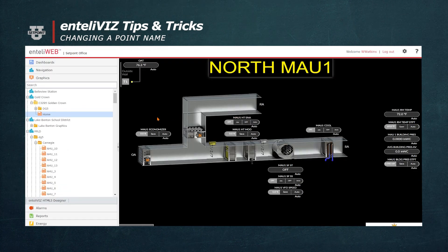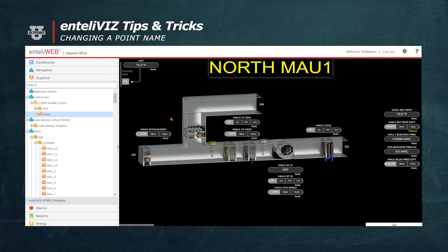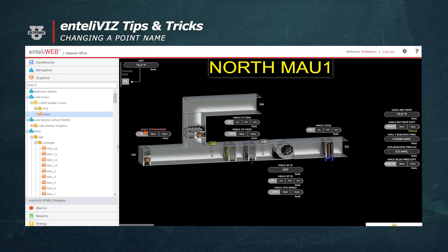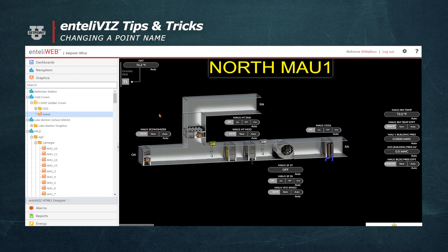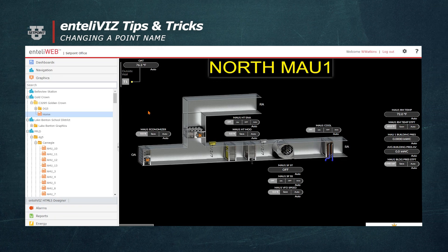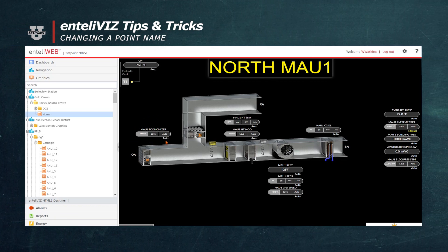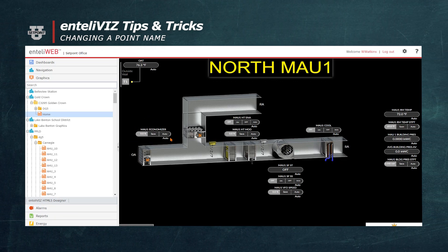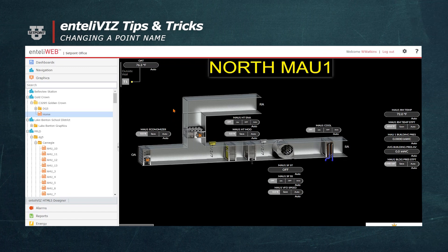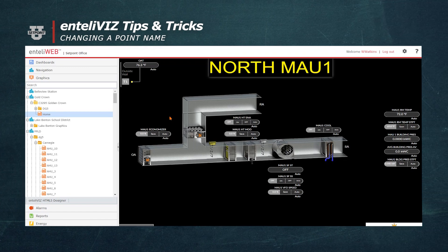This is because when these points are linked to the graphic, they assume the name of the object. It brings the name in at the same time, so in order to change it, you have to make the change at the point itself. You can do that by just clicking on the point like we saw earlier, changing the name, and then saving it. Now it will show up on the graphic.